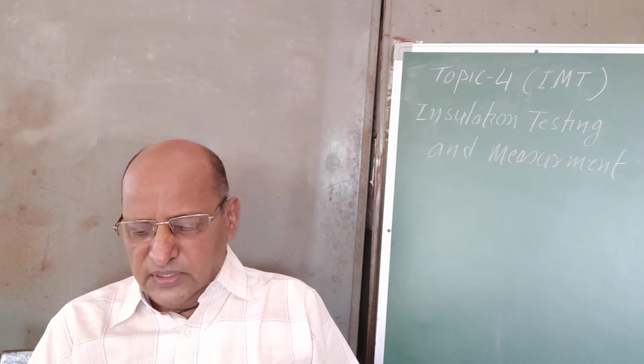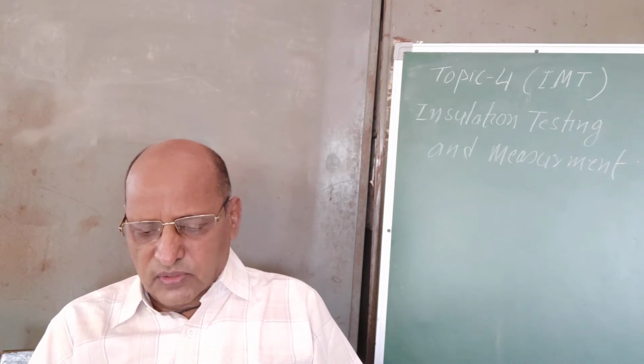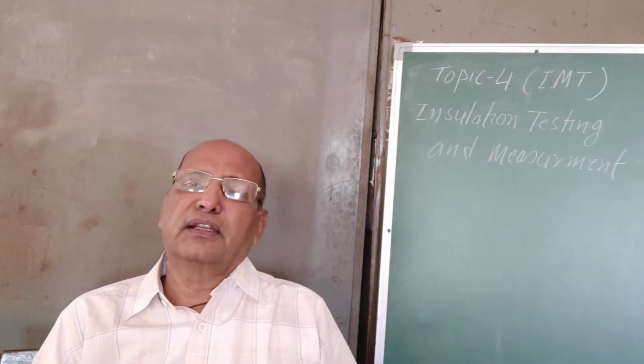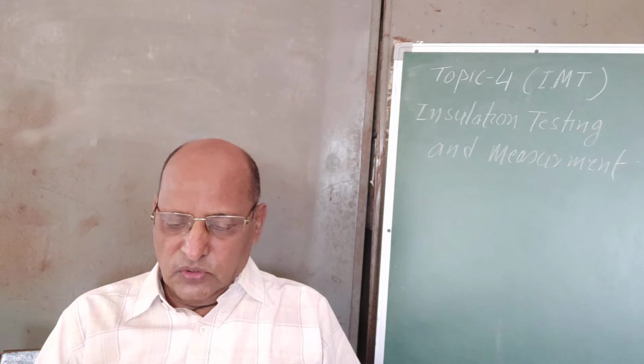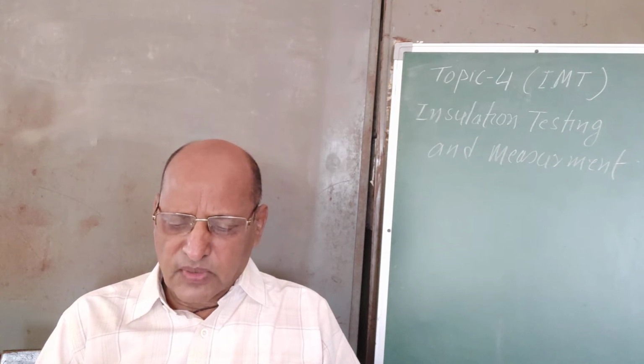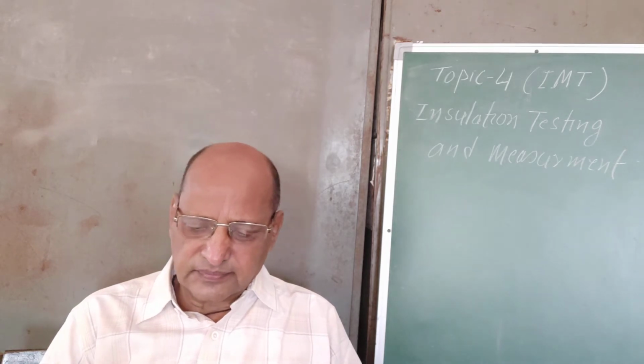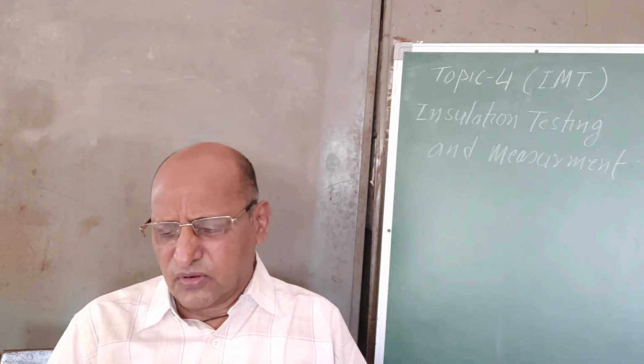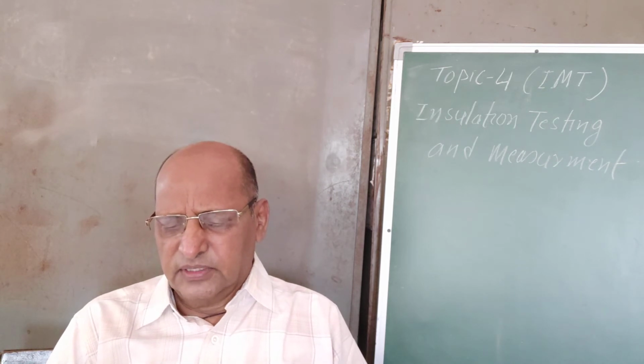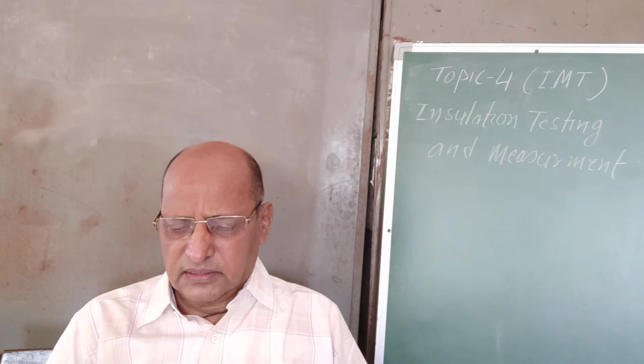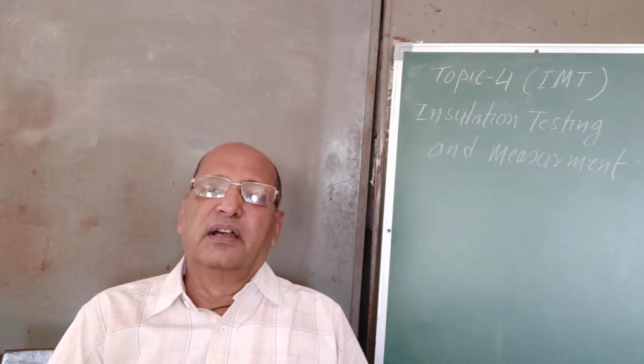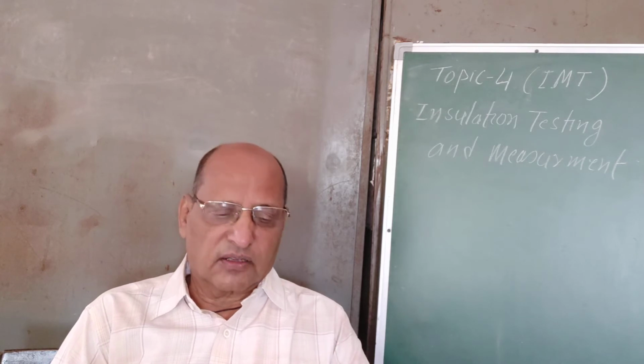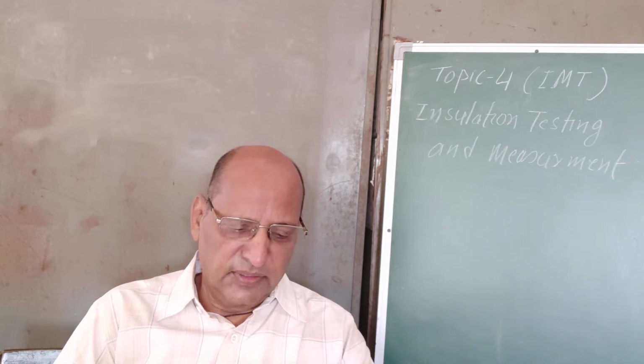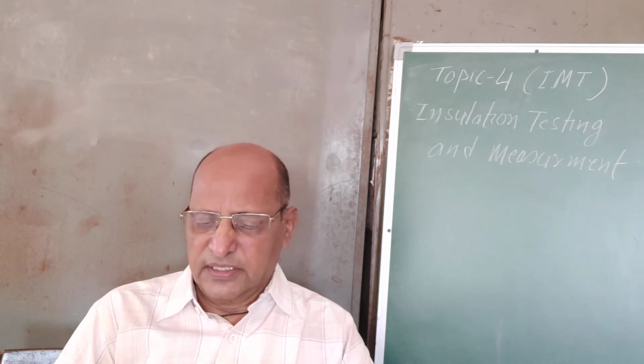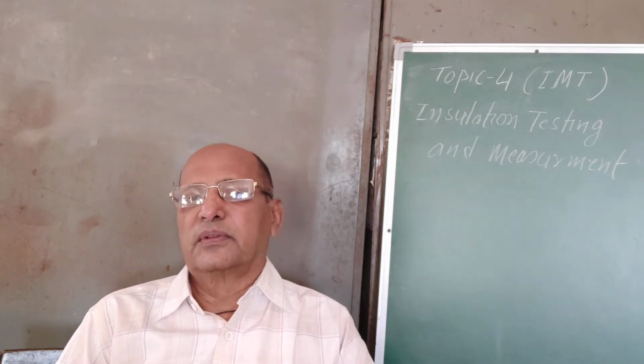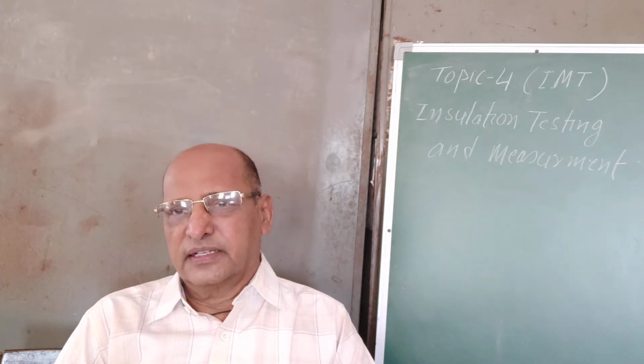Then vacuum impregnation is to be used for cotton insulation and paper insulation. There is a vacuum impregnation plant in which whatever insulating material is required in liquid form is filled into the chamber, and a vacuum is created in the chamber. Then whatever material is to be insulated, cotton or paper, is placed in it, and with a rotary action the whole system rotates along with the drum.